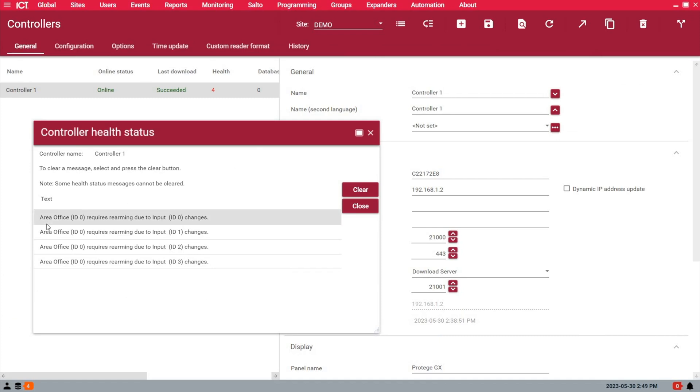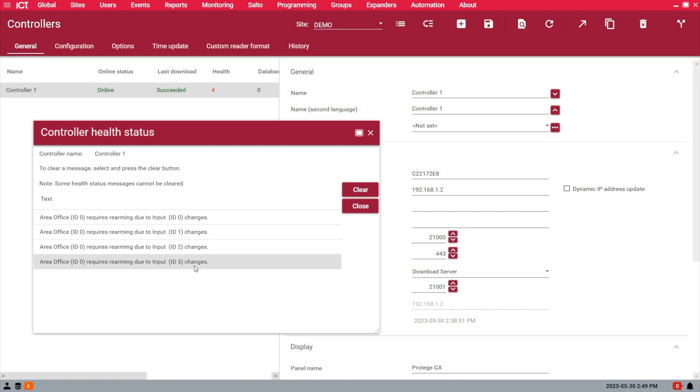At the bottom here, we see area office, which is the area I added four zones to, requires rearming because I modified input 0 to 3. I modified the first four inputs in the list. The 0, 1, 2, and 3 in brackets is the database ID of this record, so I know exactly where to look. The controller is smart enough to tell you that you need to rearm the area to apply changes.